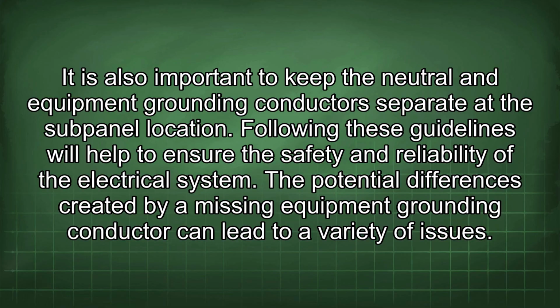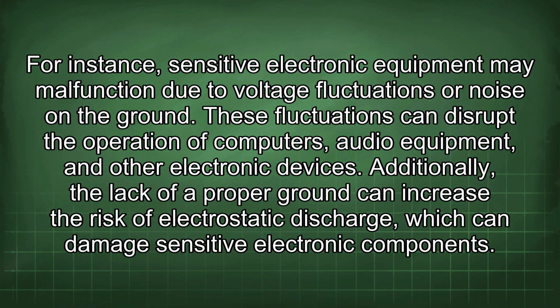The potential differences created by a missing equipment grounding conductor can lead to a variety of issues. For instance, sensitive electronic equipment may malfunction due to voltage fluctuations or noise on the ground. These fluctuations can disrupt the operation of computers, audio equipment, and other electronic devices. Additionally, the lack of a proper ground can increase the risk of electrostatic discharge, which can damage sensitive electronic components.